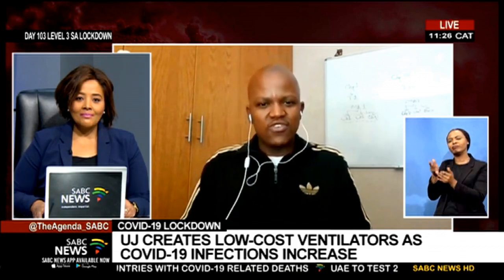Thank you for giving us this opportunity. The ventilator came about when we said that as a group of engineers we need to do something that will really help in addressing this COVID-19 problem. Prof Jan, who is the head of department in the Department of Mechanical Engineering Sciences, recruited myself as well as three postgraduate students. We took basically an ambu bag — sometimes called the bag valve mask — and we automated how that works. The way that we automated it is that we 3D printed the parts and superimposed that with electronics.